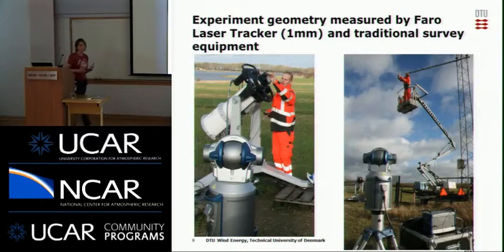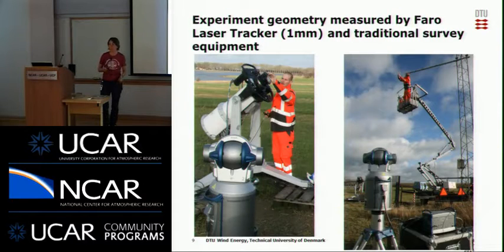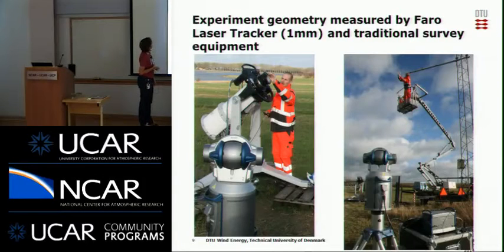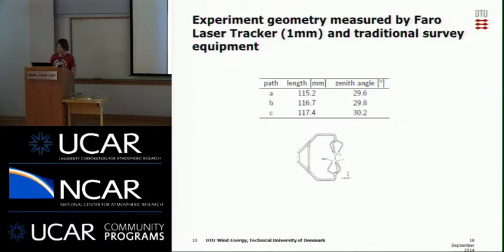And then, since the 3 wind lidars kind of form one instrument, we need to know the geometry of this instrument to a very high precision. So there was a company coming, and they used this Faro Laser Tracker equipment. You can see here he measures on the lens, so we know exactly where our beams are located. And they also measured on the sonic itself. They actually also measured the exact geometry of the CSAT, but because it was quite a windy day, and they were maybe moving a little, the transducers, so we didn't use those measurements. We used the standard CSAT settings.